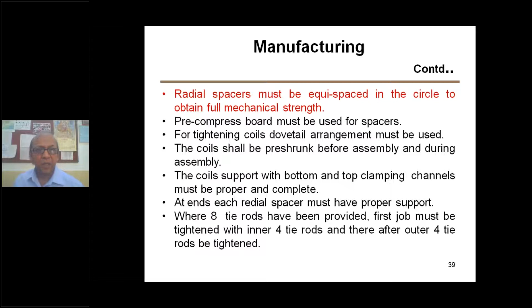Then where 8 tie rods have been provided, first the job must be tightened with the inner 4 tie rods, and thereafter the outer 4 tie rods must be tightened. This care must be taken, because then you are fully taking the advantage of 8 tie rods. Okay. Radial spacer must be equal, this is already said. Now this is the next slide.